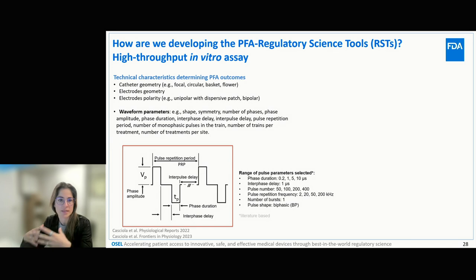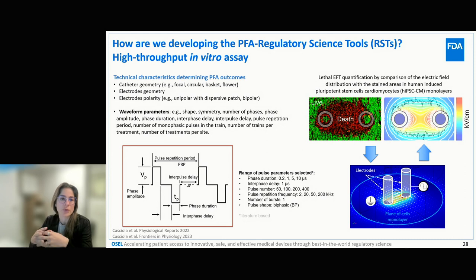We know from a scientific point of view that parameters influencing the outcome of this technology include the catheter geometry - for example, whether the catheter is focal, circular, a basket, a flower, or some other shape - the electrode geometry itself, and the electrode polarity, such as unipolar with a dispersive patch or bipolar electrodes. One of the key players is the waveform characteristics and parameters.